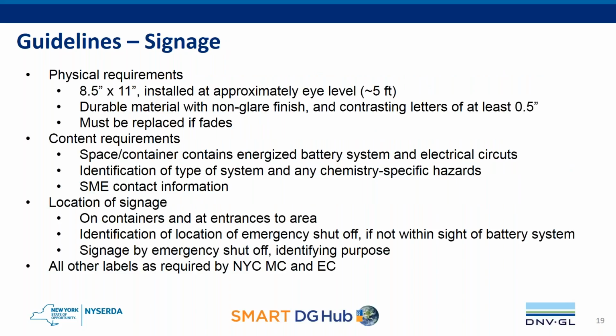And finally, for signage, I don't think any of these will be a big shock, but there are physical requirements for the signage: the size of the signs, the material that it's made of, and it must be replaced if it fades. The content does need to note that the space contains an energized battery system and identify any chemistry-specific hazards. For instance, for a sodium-type battery, not to apply water.